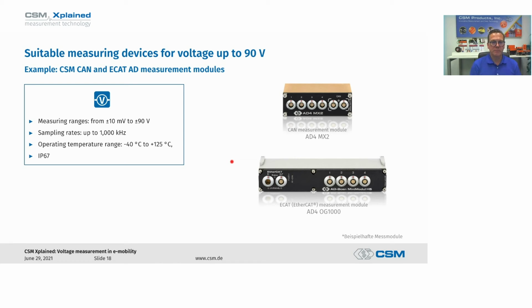When we say ultra low, this is really in the millivolt range where you're detecting a change in some physical attribute as detected by a sensor. Or you could take the working voltage up to 90 volts. As Paul showed in the coffee maker example, that voltage can drop and spike and then settle down with AC components as a device does its task, whether that's a coffee maker or a battery thermal management system on a vehicle. They all perform very similarly, so you need very fast sampling rates. We can do that on the EtherCAT bus with up to 1 megahertz sampling rate, and we're known for our rugged and compact IP67 form factors for those modules.